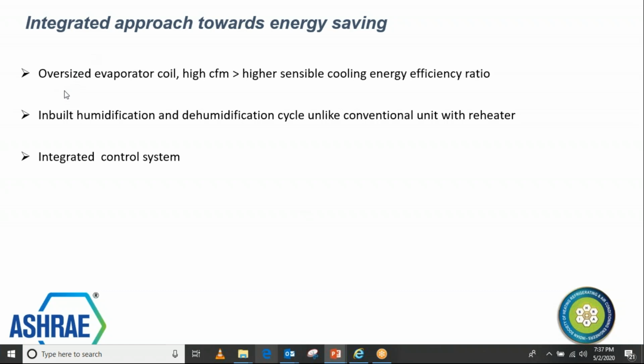The system approach, when you go to the integrated side, is another basic difference, in how these systems are running. This makes a lot of difference when you have more number of units installed in the room. But even at every component level, even if it's a one-to-one system, the evaporator coil and the unit, along with the compressor and the condenser, the entire system is running through an integrated control. And obviously, as I have already discussed in the previous slide, the oversized evaporator coil and high CFM AC fans deliver better sensible heat ratio and better energy efficiency ratios, with a built-in heater, humidifier and built-in dehumidification cycle. Unlike in comfort, where you put in a reheater, and the reheater comes into action when humidity control is required.